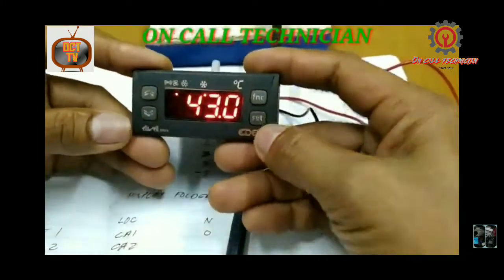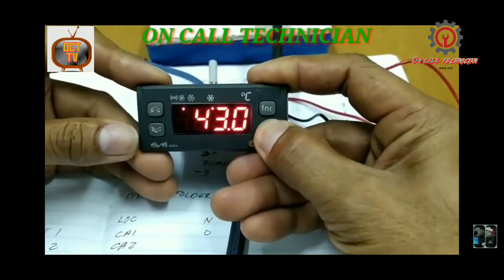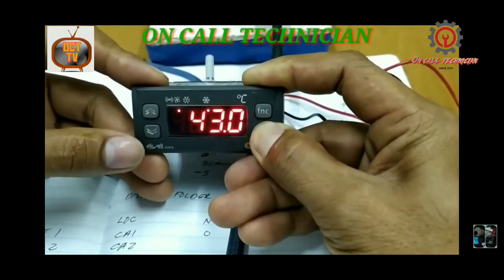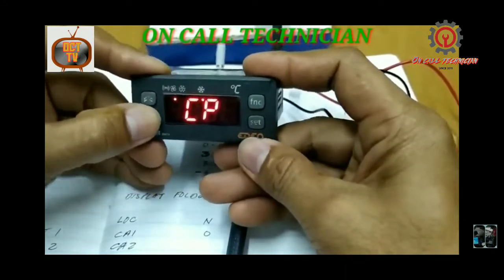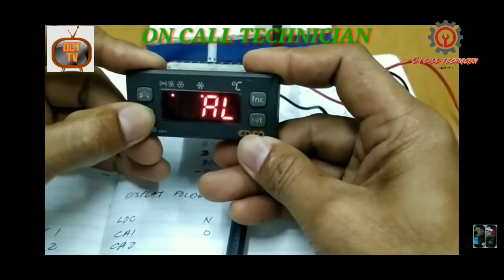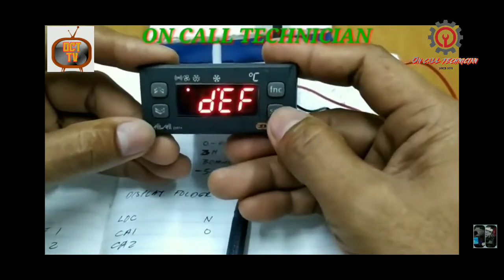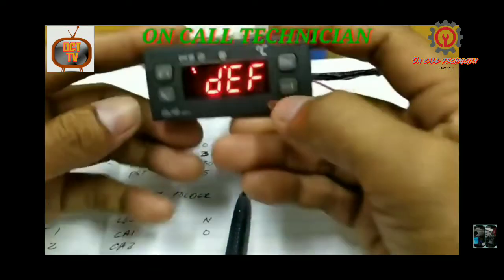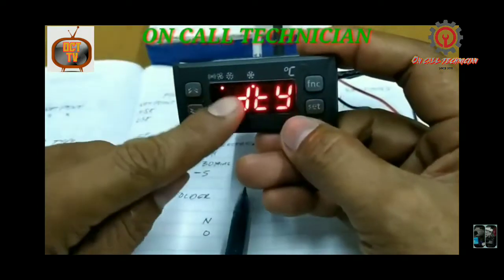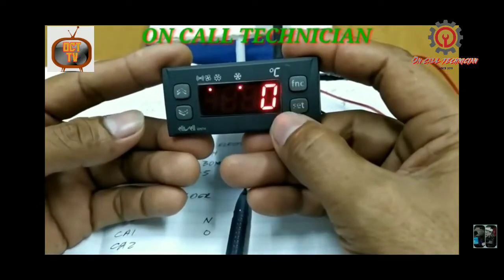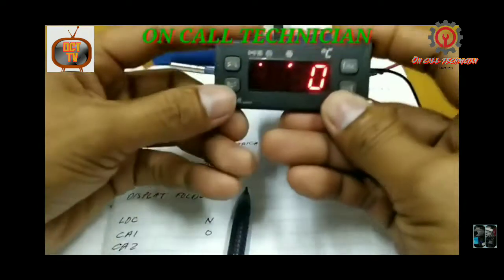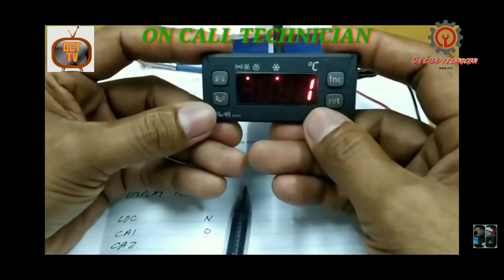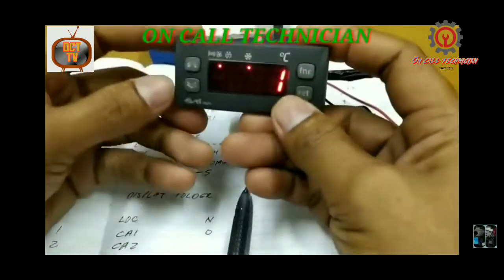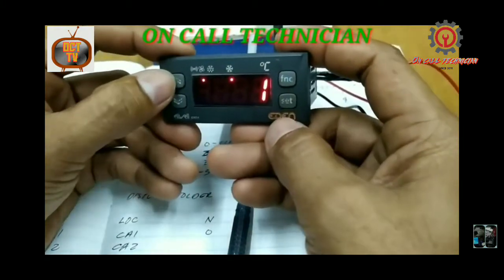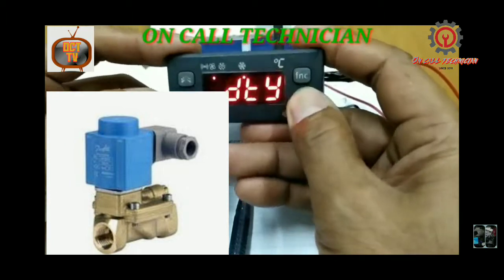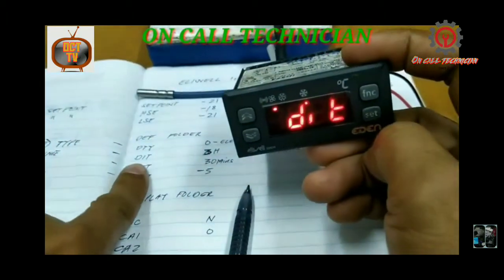Okay, so let's enter the programming mode again by pressing the set button. 1, 2, 3, 4, 5, 6, 7 seconds. Under the CP, let's change it to DEF folder. Press set and let's change it. Okay, so this is defrost folder. Okay, under the DTY, press set, and the value is 0, and this is electrical defrost, guys. Okay, just if you want to select the number 1, this is the inversion. Okay, inversion is using solenoid valve.